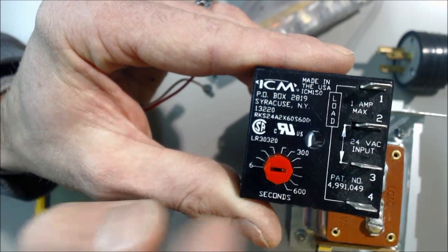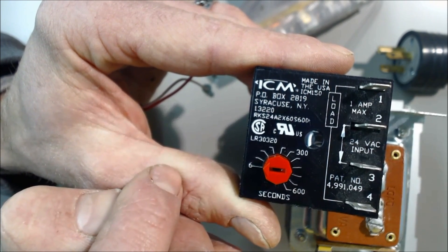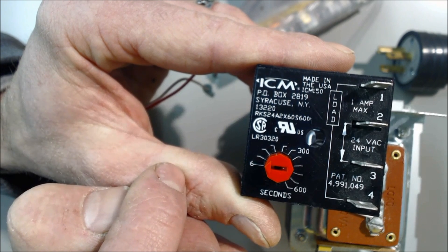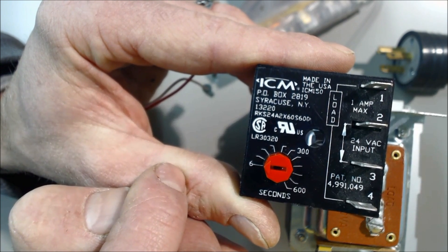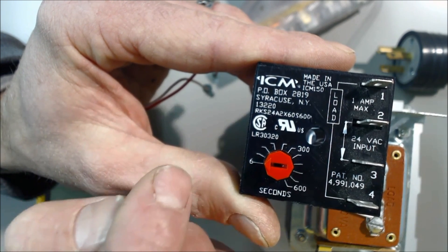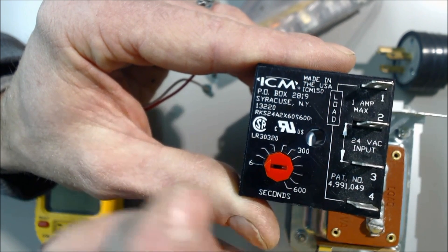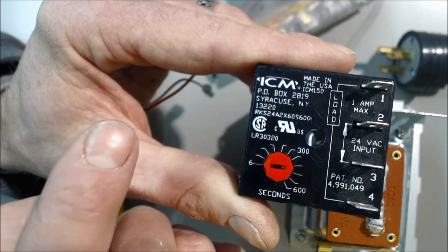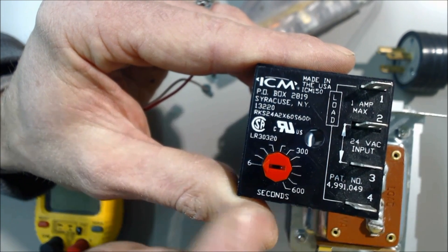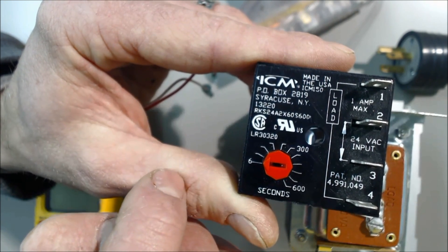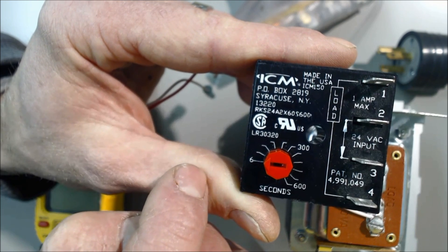your compressor is susceptible. I've seen compressors and had to change compressors out because whoever installed it did not have a thermostat with a five-minute on-delay. What would happen is the thermostat would call for cooling, and then that compressor would shut off, and then all of a sudden it would call for cooling again. It did not have a chance to equalize and therefore ended up ruining the compressor.